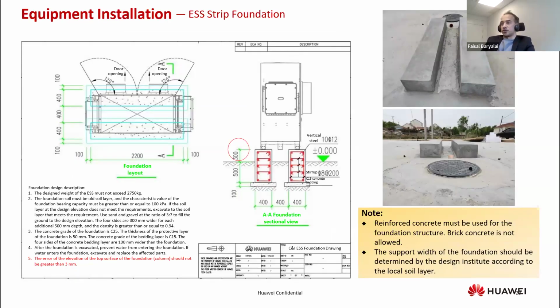Yes, about installations, that's also a question which comes a lot to our support service email every day. What are the recommendations? Should this battery be installed indoors or outdoors? Especially for Scandinavia, which could get cold outside. So that's also one of the questions we get: is it possible to have the battery in a cold climate? Of course, this battery has an IP class, and it is meant for very low temperatures, even -20. Even if it's -20 for our outdoor installations, there is a heating system, the AC system, which maintains the internal temperature of the cells in the battery. So we can have it outdoors, which is an easy alternative to install the battery. And these are the dimensions of this foundation.